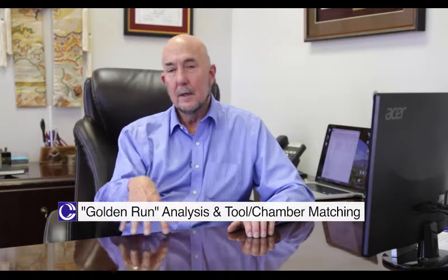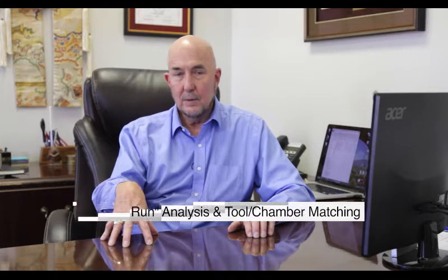Of course, another thing that once you understand the tool's behavior and have a good fault detection application, you then start to use it to compare tools across a fleet. A set of similar equipment you want to have behaving in the same way, and maybe you have one that behaves very well, but you're not quite sure why. So you do what's called a golden run analysis on that equipment, and you compare the key trace variables in one with like variables in similar equipment to see where the differences are and perhaps why those differences exist.